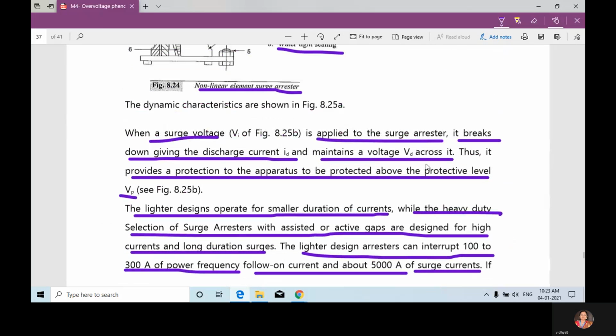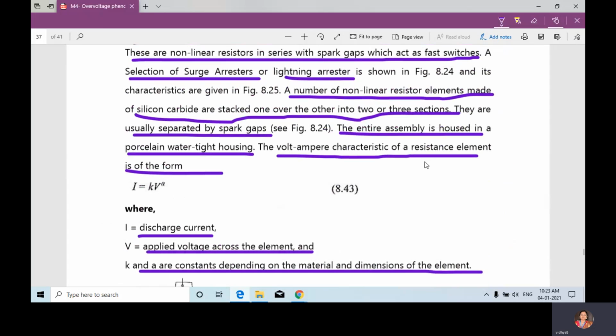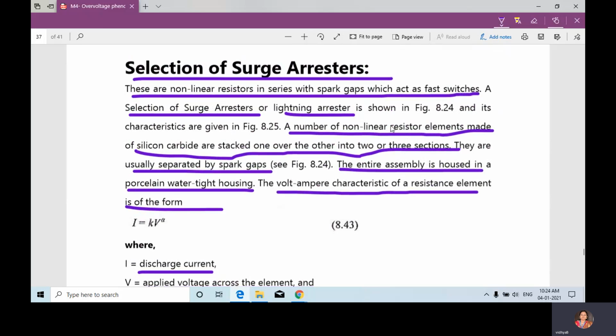Okay. These are the points we need to remember for selection of surge arrestor. First, we use non-linear resistors in series with the spark gaps, which act as fast switches. Next, a number of non-linear resistor elements are made of silicon carbide and are stacked one over the other into 2 or 3 sections.